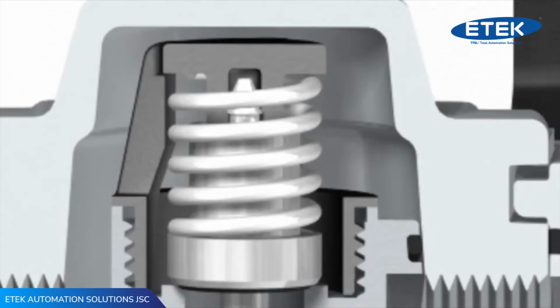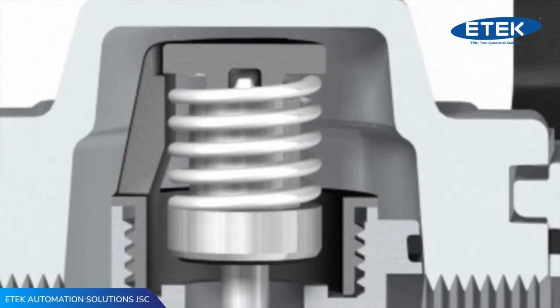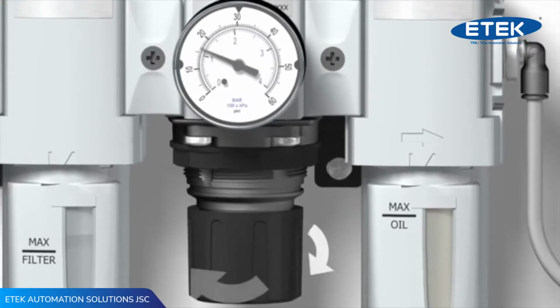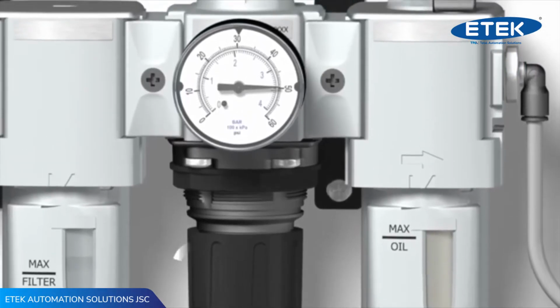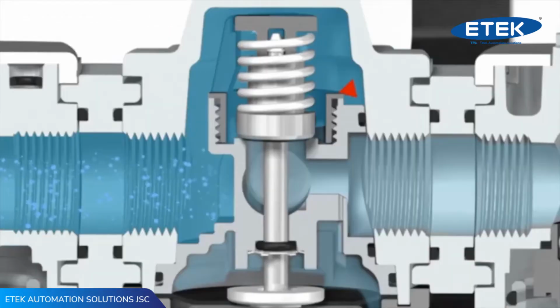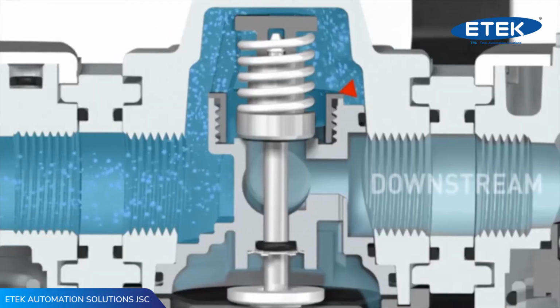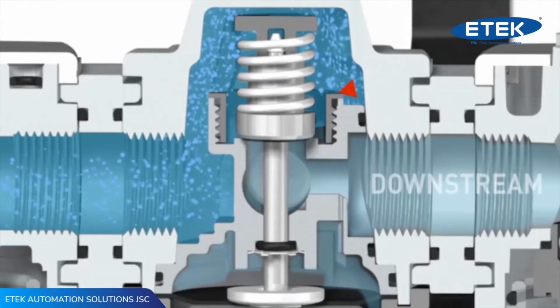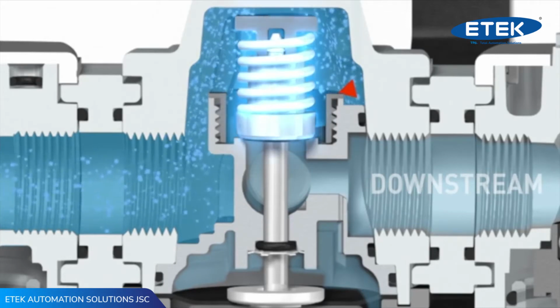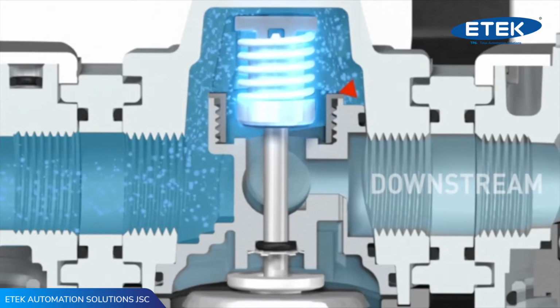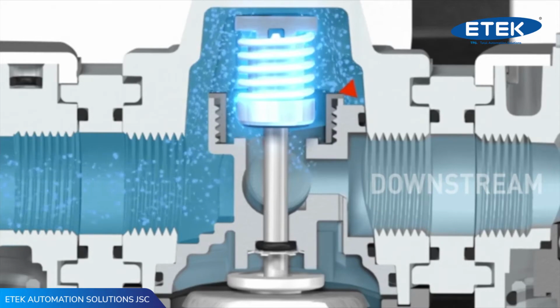The regulator achieves this using a spring-loaded assembly. The knob on the regulator adjusts the force of the control spring to achieve a desired pressure set point. Whenever the downstream pressure level drops lower than the desired set point, the poppet, or internal valve, opens a pathway for the higher pressure upstream to flow downstream.